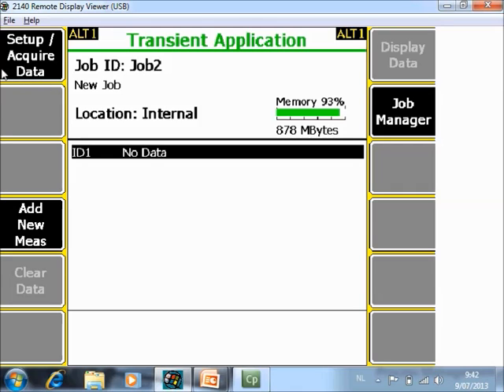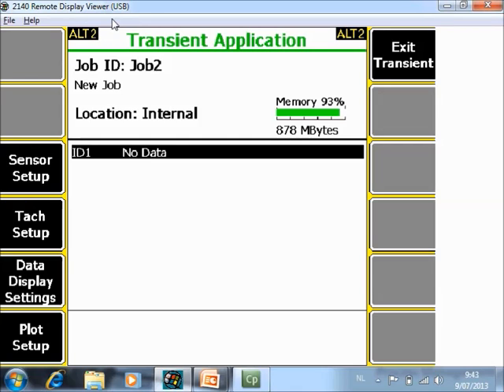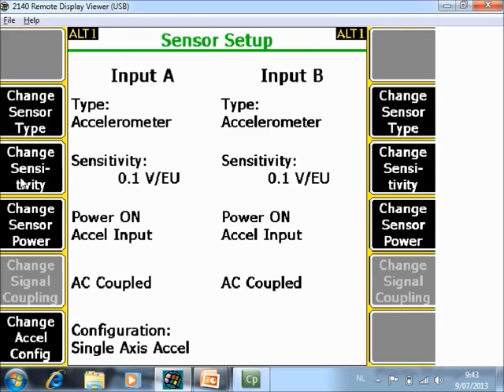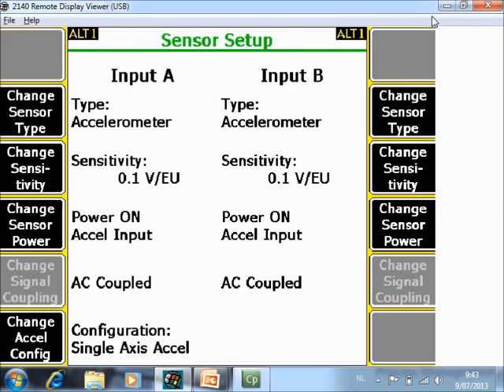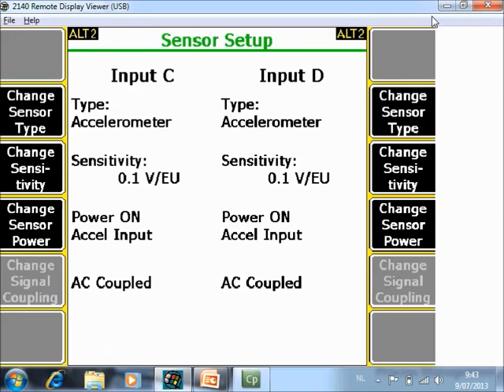Normally you have to go to setup acquire data to configure what and how you want to configure it. However, there are a couple of one-time settings that we have to double check now. If you go to the alt 2 page, there are a few one-time settings. First of all, when you go to sensor setup you can check if you are using everywhere on all your channels the right sensor. If not, you can change it here. In alt 1 and alt 2 are the 4 sensors.